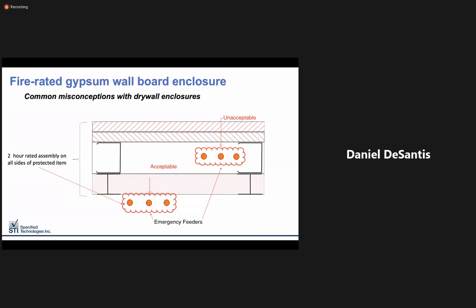The correct method of enclosing using drywall is to build a full depth assembly on all sides of the protected item. As you can see, these 3 emergency feeders shown in red are behind a shaft liner side of the wall. The double layer gypsum would be considered your exposed side, and 3 more sides like it must be constructed to have a full 2-hour rated assembly.